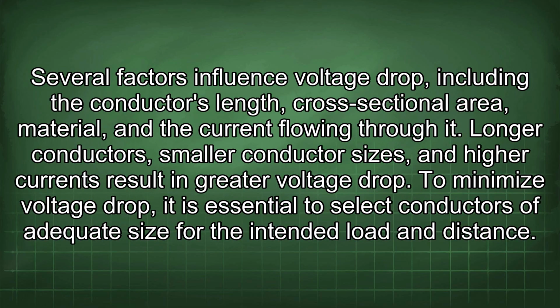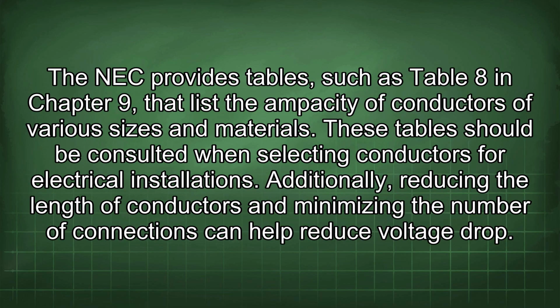Several factors influence voltage drop, including the conductor's length, cross-sectional area, material, and the current flowing through it. Longer conductors, smaller conductor sizes, and higher currents result in greater voltage drop. To minimize voltage drop, it is essential to select conductors of adequate size for the intended load and distance. The NEC provides tables such as Table 8 in Chapter 9 that list the ampacity of conductors of various sizes and materials. These tables should be consulted when selecting conductors for electrical installations.